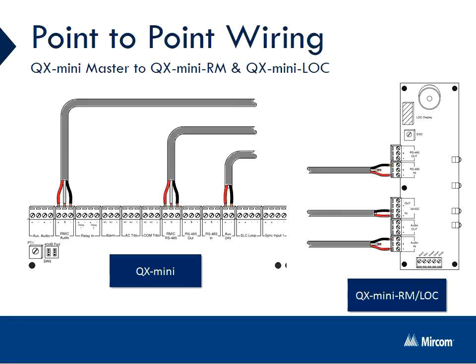For the R-Mic audio and R-Mic RS485 connections, make sure that the shield wiring is only connected on the output terminals and do not connect the shield to the R-Mic audio and R-Mic RS485 inputs.